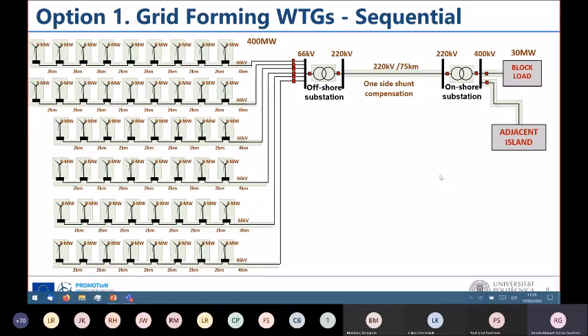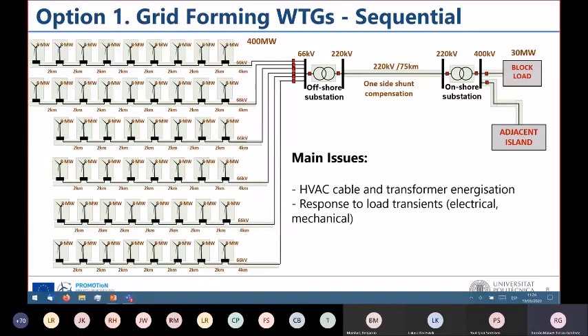Which are the main issues here? The first one is obviously long HVAC cable and transformer energisation. This is quite challenging due to inrush currents and also due to resonances. The second issue is what happens if we have changing block loads, which is going to happen in this kind of situation. What are going to be the effects on the electric system, and more importantly, what are going to be the effects on the mechanics of the wind turbines if all the loads are going to be shared equally between all the wind turbines?